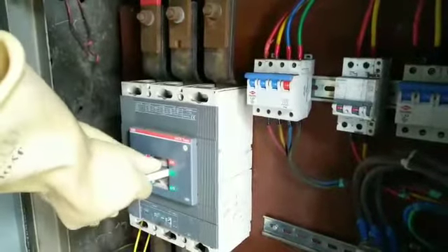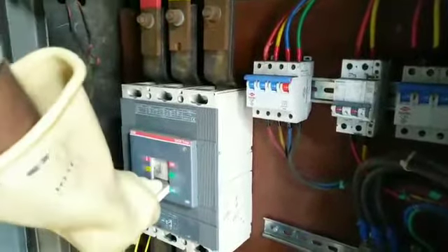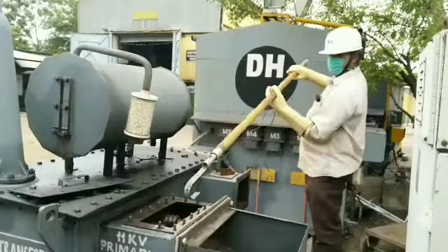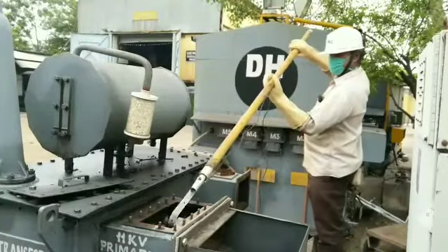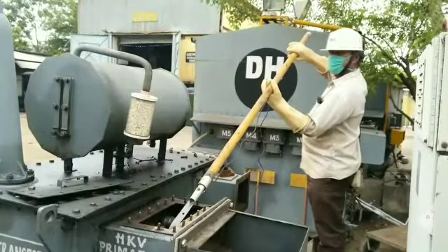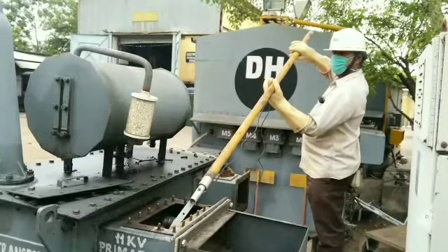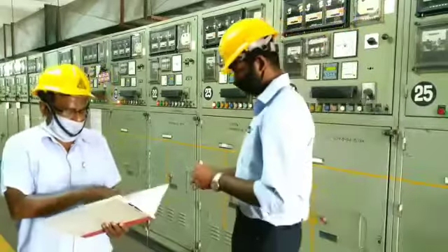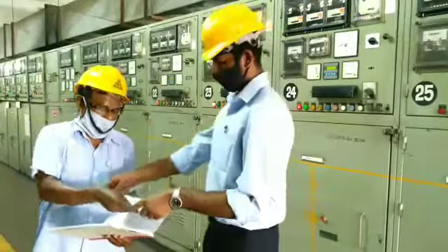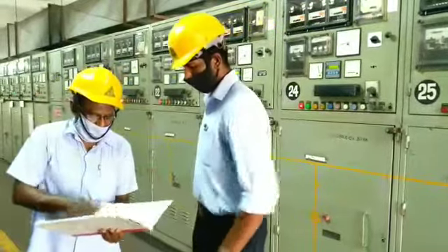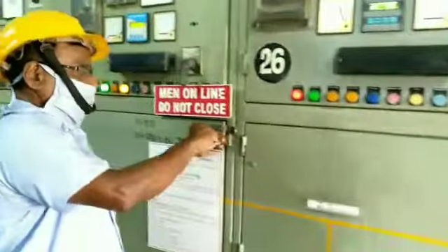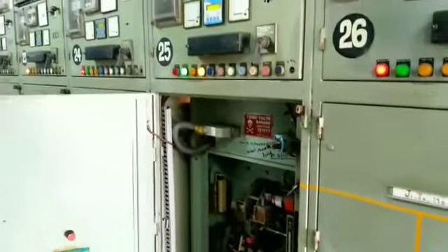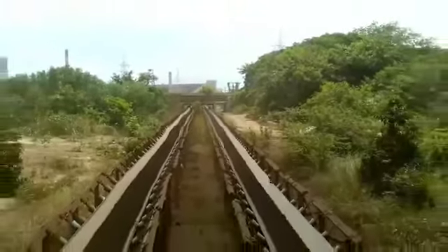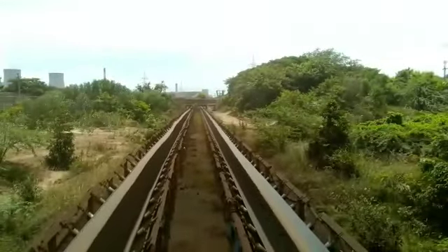Switch off the transformer primary and secondary breaker. Open the transformer primary side cover and connect the earth rod between the primary terminals and earth to discharge the residual current. After completion of work, return the line clearance to the substation in charge, unlock the control panel, close the isolator and switch on the breaker. With a long siren, start the system with a small jerk and continue the production.